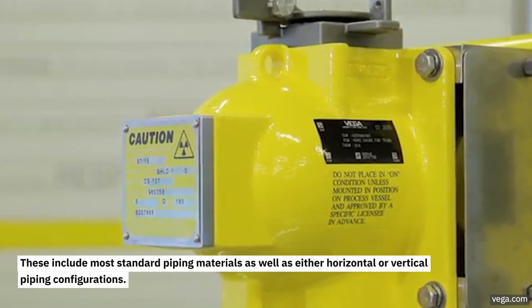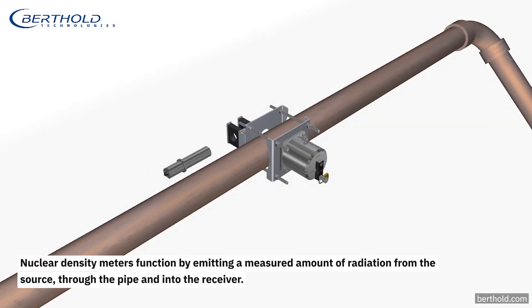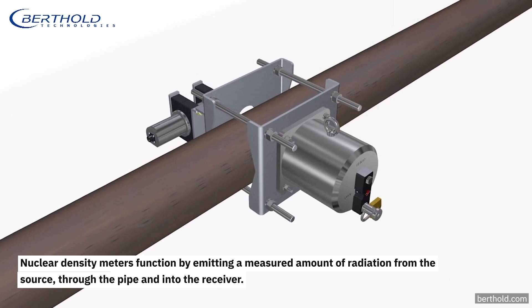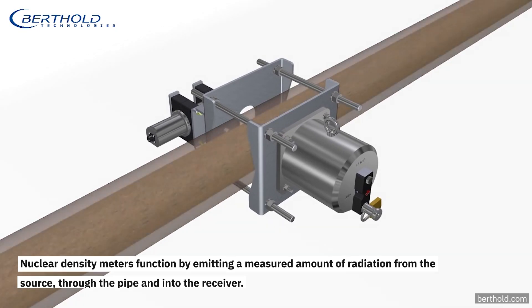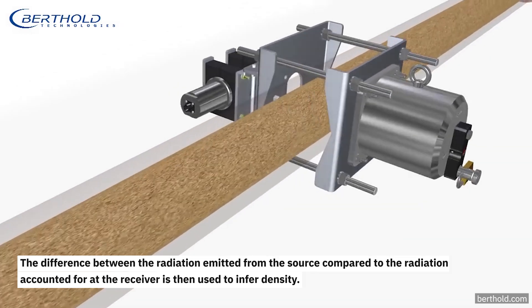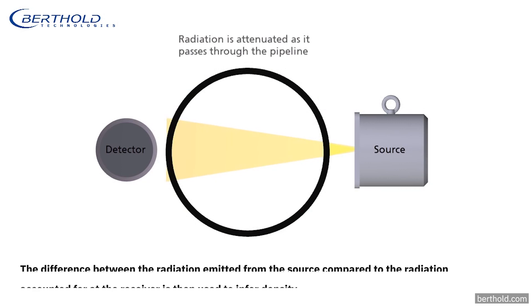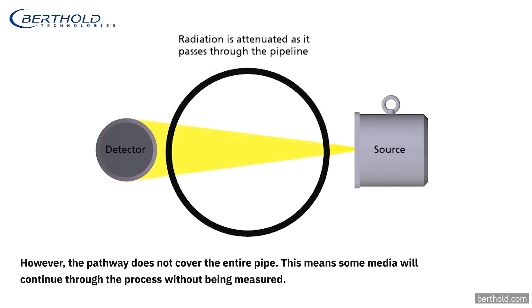Nuclear density meters function by emitting a measured amount of radiation from the source through the pipe and into the receiver. The difference between the radiation emitted from the source compared to the radiation accounted for at the receiver is then used to infer density. However, the pathway does not cover the entire pipe, which means some media will continue through the process without being measured.